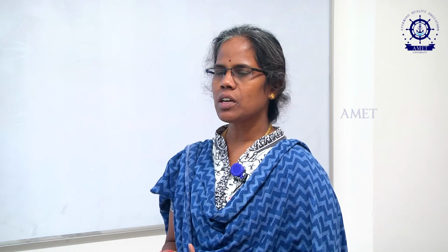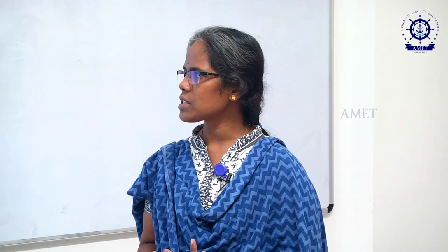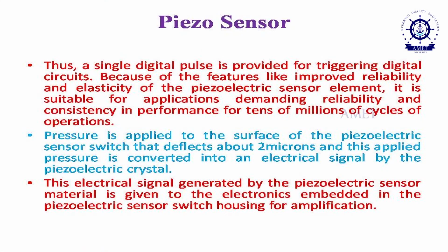For that reason, the elasticity of the piezoelectric sensor element is suitable for demanding reliability and consistency in performance for tens of millions of cycles of operation. When pressure is applied to the surface of the piezoelectric sensor switch, it deflects about 2 microns, and this applied pressure is converted into an electrical signal by the piezoelectric crystal. This piezoelectric crystal acts as a small electrical switch.